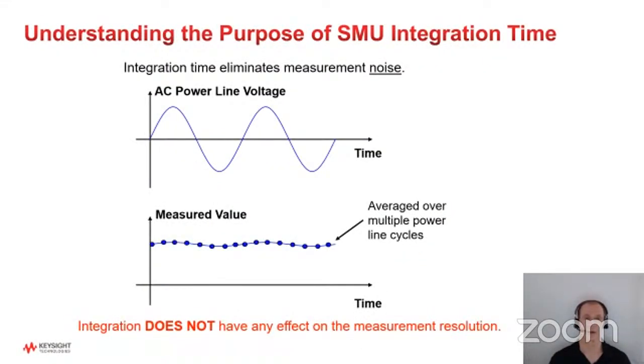So I want to make sure that everybody understands the purpose of SMU integration time, what it really does. And again, integration time is there only to eliminate noise, and it does this by averaging out. It takes multiple measurements over some time period you specify, and it averages them together to eliminate noise. Now, what's the most prevalent source of noise in a lab? Typically, it's power line cycle noise from the AC voltage powering up your instruments. And that's going to be either 50 or 60 hertz, depending on what part of the world you're in. And by the way, most instruments do have a setting somewhere hidden in them where you tell it whether it's 50 or 60 hertz. So be careful that you know about that, and check to make sure it matches your country's spec.